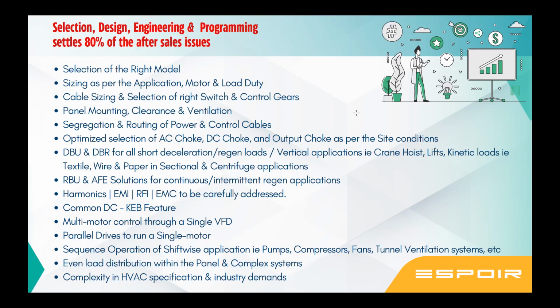Chokes, I explained. DBU, DBR, I explained. And DBU, DBR is mandatory for any vertical application. Please keep that in mind. Any vertical application like a lift, crane, hoist, conveyors, any application where the motion is vertical, the motor should have a brake by default. Your drive should have a brake release logic only after torque is generated in the motor. Otherwise, if you simply open the brake and start running the motor, and the load is there but the torque is not available, gravity is going to pull the whole system down, and it can create an accident.